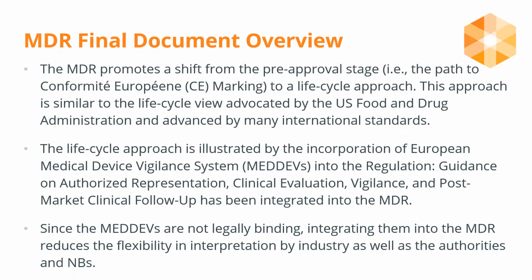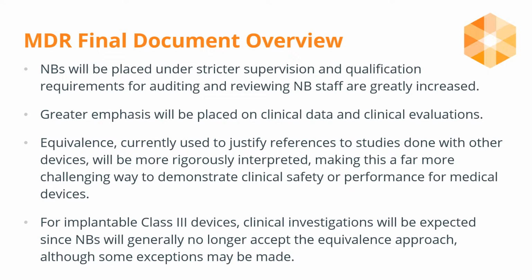The MDR final document promoted a lifecycle approach, which is mirrored after the US FDA and other international standards. This lifecycle approach incorporated the European Medical Device Vigilance System into the regulation. Since they are not legally binding, integrating them into the MDR reduces the flexibility in interpretation by industry. Notified bodies will have stricter qualification requirements and be under stricter supervision.